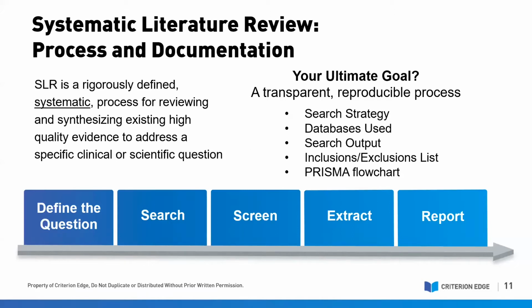The data extraction is the stage in the process in which you've identified the articles that contain specific data relevant to your performance criteria. And in the case of many IVDs, their performance criteria may encompass data such as sensitivity or specificity, false positives or false negatives, or limit of detection. And then in the end, you must present the data that's been extracted, but you're also expected to report on the process that we undertook to arrive at this data. So remember, we are looking to prove the association of an analyte with a clinical condition or a physiological state.